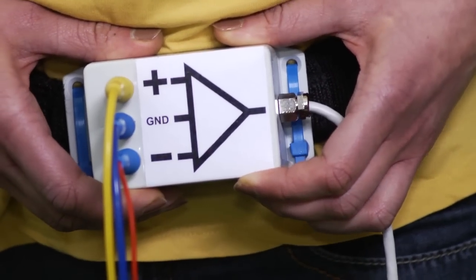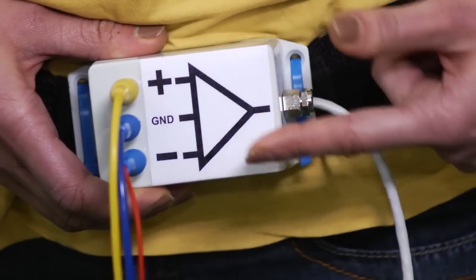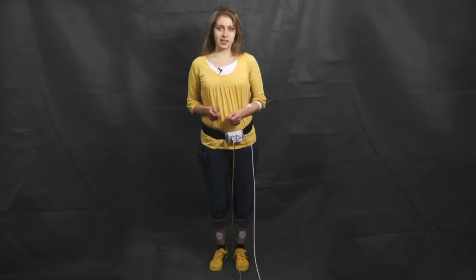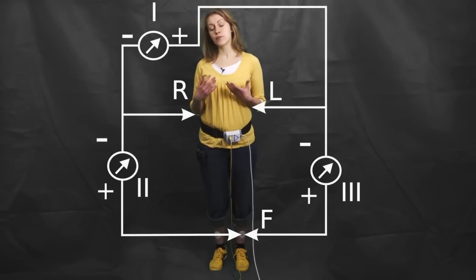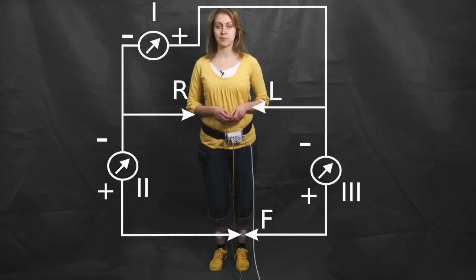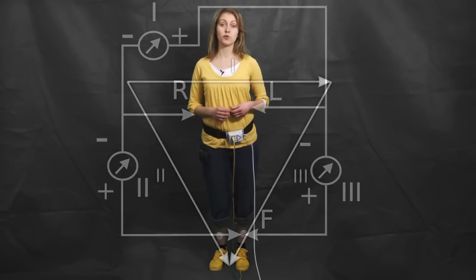Remember that every bioamplifier has got three inputs: positive, negative, and ground. And these need to be connected to my limbs for the Einthoven ECG. The convention is to use the left arm, the right arm, and the left foot for the electrode placements. This gives us three combinations, or three different signals, called Einthoven leads 1, 2, and 3, which can be symbolized by the famous Einthoven triangle.